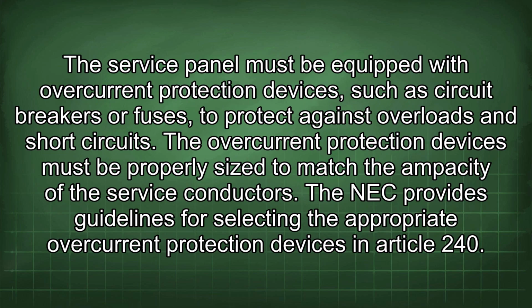The service panel must be equipped with overcurrent protection devices, such as circuit breakers or fuses, to protect against overloads and short circuits. The overcurrent protection devices must be properly sized to match the ampacity of the service conductors. The NEC provides guidelines for selecting the appropriate overcurrent protection devices in Article 240.